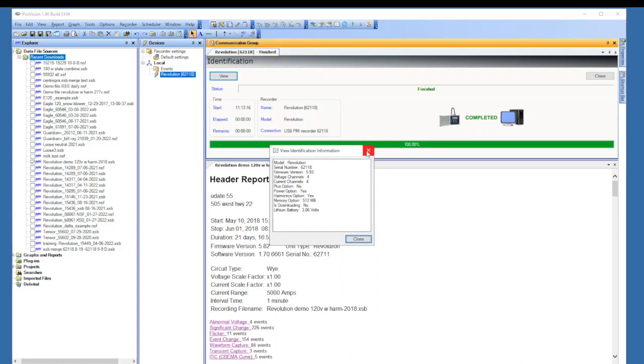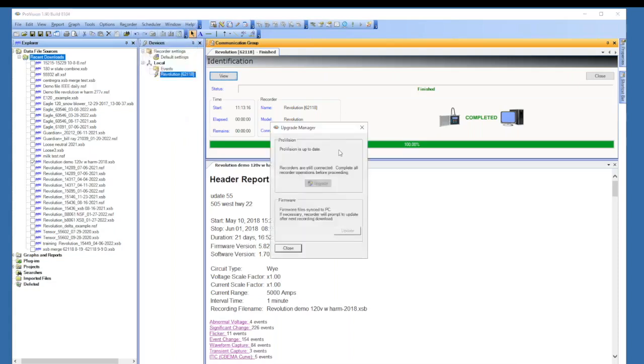There's also a firmware version for the recorders. If you go to the Help tab, there's a check for updates. So if a new ProVision is out there and you're on the 1.90, you can click on the upgrade. And usually without any admin rights, it can go in and just upgrade a few files. You'll also find that there's firmware available. You want to upload that to your PC or laptop. And then when the recorder is connected, it compares the firmware that's on your recorder to the firmware that's in your ProVision. And if the recorder is behind in that firmware, the next time you download it, you'll be asked to update that firmware.